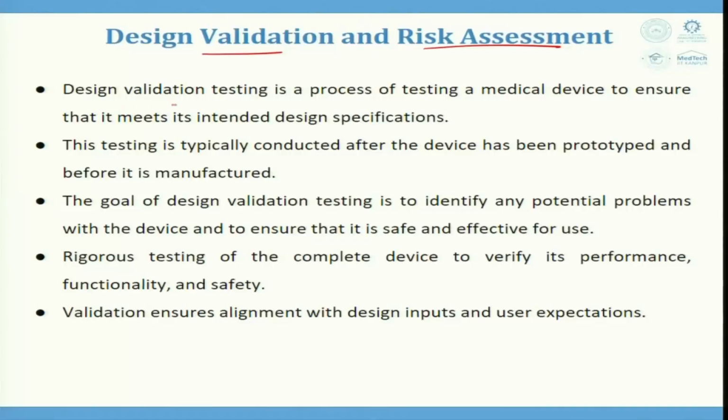Now, design validation testing is a process of testing a medical device to ensure that it meets its intended design specifications. This testing is typically conducted after the device has been prototyped and before it is manufactured. So, between prototyping and manufacturing, prototyping means we try to develop only a few prototypes. A full-fledged manufacturing setup is not made.